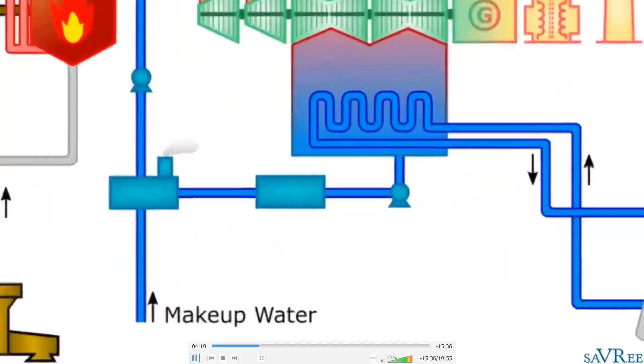So let's have a look at our water circuit now, because it's water that gets fed to the boiler in order to generate steam. We've got a make-up water inlet. The make-up water feeds to a deaerator. When we talk about make-up water, we're essentially talking about the water that's added to the system and then treated before it becomes boiler feed water. You can't just take water from a city grid or from a lake or a river and put it into a water tube boiler. That's not going to work. You're going to have a lot of corrosion and a lot of problems.